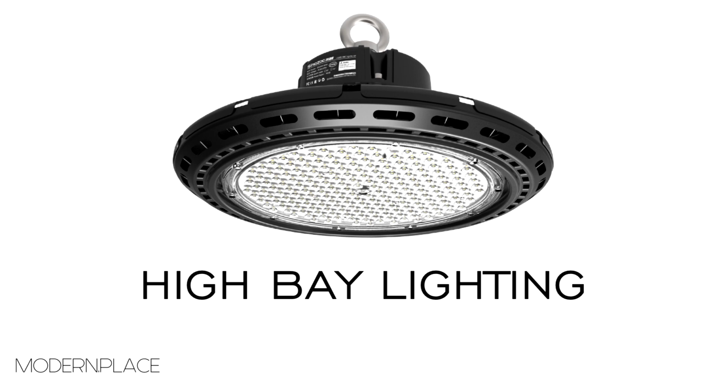Moving on, I wanted to talk about the color temperature of the UFO high bay lights or any kind of lights and what effect it has on efficiency. Essentially, for commercial and warehousing, you don't really need to worry about color temperature, except that you want it to be between 4500 and 5500 Kelvin. That's when LEDs are the most efficient, and that's generally what you want to stick with, because if you go into those extreme yellow lights, such as 2700 or 3000 Kelvin, you're losing about 10% to 20% lumen efficiency up front. So you're essentially throwing money in the garbage just because you want a warmer light.